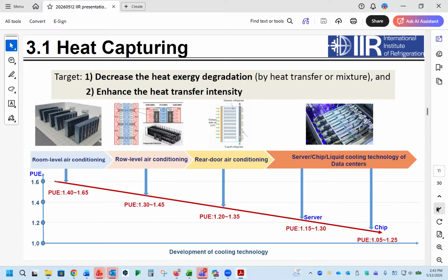Originally we used room-level air conditioning systems, but their PUE is usually a bit higher, ranging from 1.4 to 1.65. To increase efficiency and decrease PUE, we use row-level air conditioners, which result in PUE decreasing to 1.3 to 1.45.